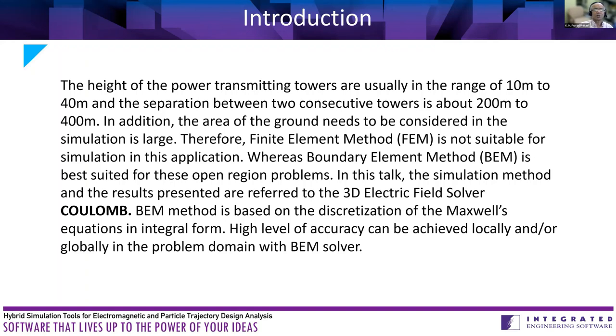The height of the transmission towers is usually in the range of 10 meters to 40 meters. If very high voltage, something like 300, 400 kV lines, there the tower height will be as high as 40 meters. And consecutive distance between the towers, anywhere between 200 meters to 400 meters.